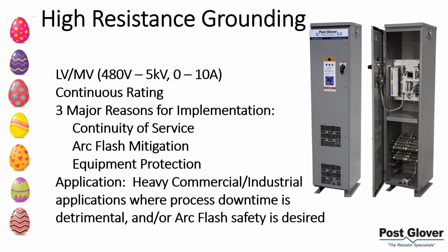Really, when we talk about high resistance grounding, usually we're talking about continuity of service. So we're looking to not trip on a fault. We're looking to just alarm. So that's one of the three major reasons. Arc flash mitigation, especially at low voltage. I've already mentioned it before. Electric Waste talked about how there is no arc flash potential on your ground faults. So you get the idea there.